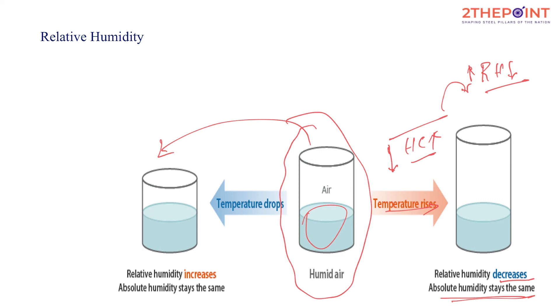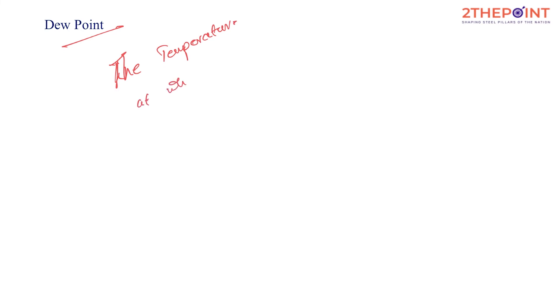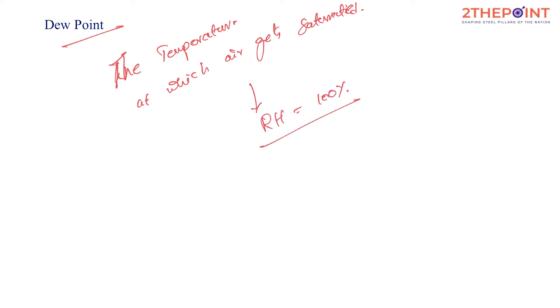The next part is dew point. Dew point is the temperature at which a unit volume of air gets saturated — that is, when the relative humidity becomes 100 percent. When relative humidity becomes 100 percent the air is said to be saturated. This is the dew point. If the temperature drops further, relative humidity would become more than 100 percent — beyond this the air is supersaturated.